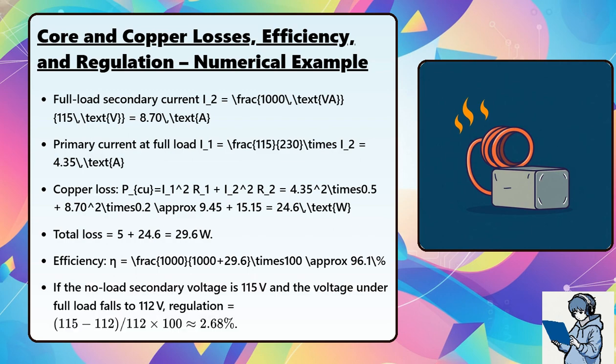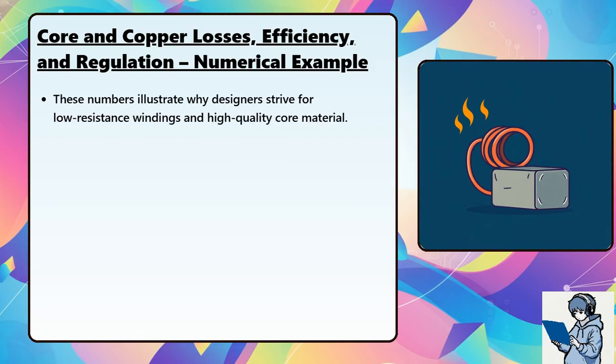If the no-load secondary voltage is 115 volts and the voltage under full load falls to 112 volts, regulation equals the difference of 115 minus 112 divided by 112 times 100, approximately 2.68%. These numbers illustrate why designers strive for low-resistance windings and high-quality core material.